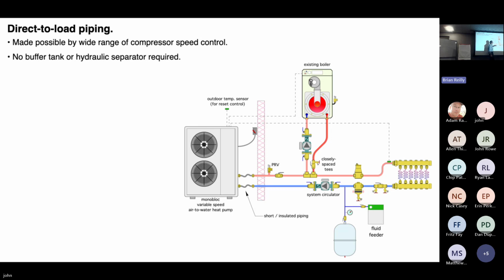This circulator is on. This warm water that's coming back from the distribution system is still going through the heat pump, so there's going to be some heat loss there. Can you control that heat loss? Yeah, to a degree. Short pipe lengths, good pipe insulation. If you're running the system on outside reset control, that'll minimize that water temperature. Under those conditions, I think this is acceptable.